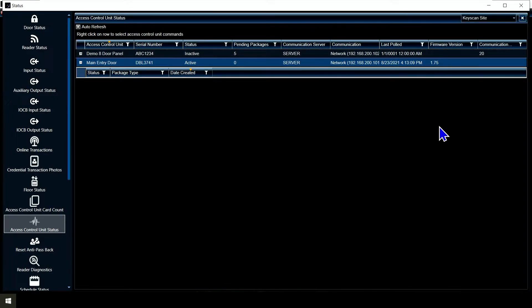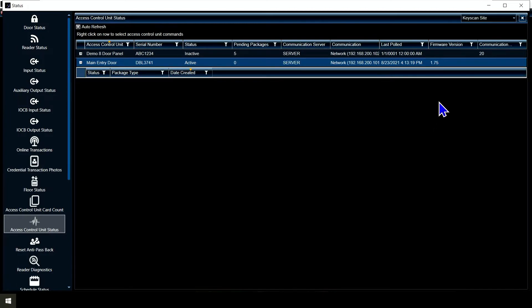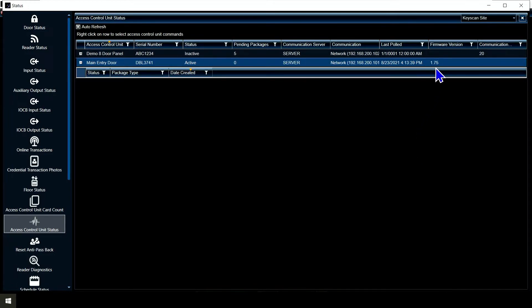If I look at this and I see it's version 9.46 or 9.47, I know that the firmware chips either have not been changed out in the panel or the dip switches were not set for integration mode. That's one of the things I look for when people say they're not communicating. I ask them what firmware version it shows. If it's 9.4 something, they haven't changed chips or flipped a switch, or they don't have integration mode turned on in the software.